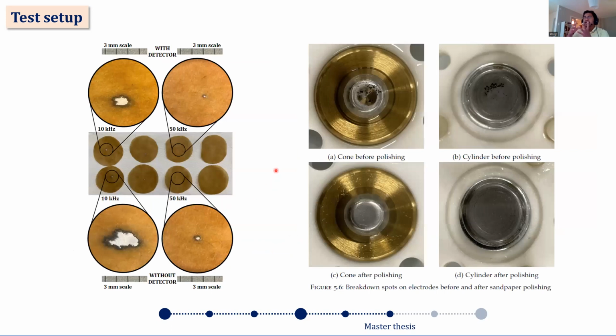If you remember, I mentioned there was like a breakdown detector. So the thing is, when the breakdown happens, you're essentially short circuiting a current through the oil paper sample. And if you allow this current go on for too long, then you would have very aggressive burn marks. And this would cause a lot of these dots on the electrode, which would then have to be polished.